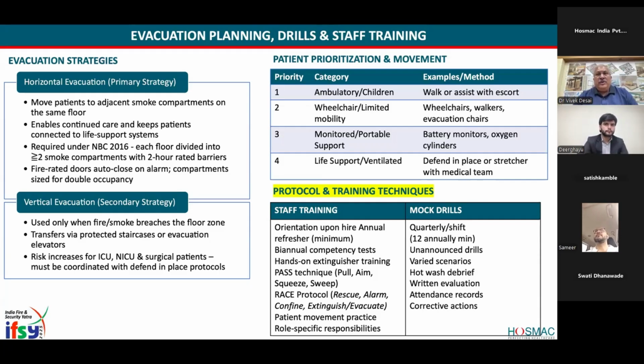A monitored patient on a bed or a stretcher has to be taken down, then we need batteries, because you have to monitor the patient as well, and also an oxygen cylinder, which needs to be taken below the bed. So all those things have to be in place. That is why they don't allow more than 30 meters for critical care, which probably one can follow. But ambulatory and non-critical patients probably should be allowed beyond 45 meters with a proper evacuation system and firefighting systems. But the most important is the protocol and training techniques.